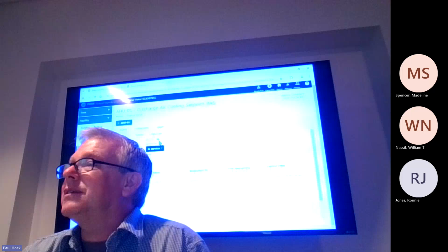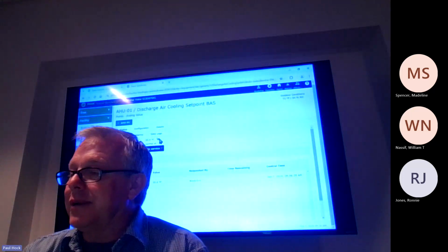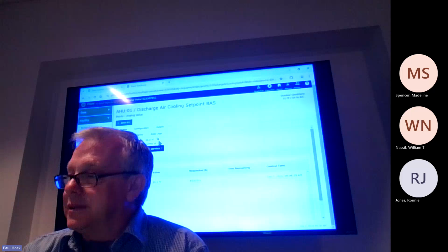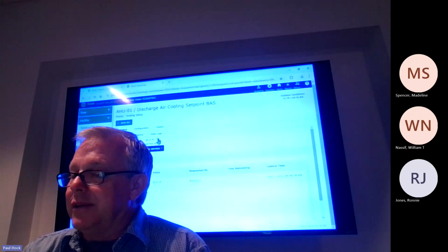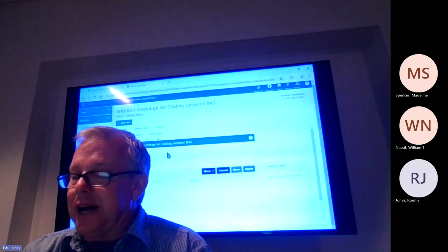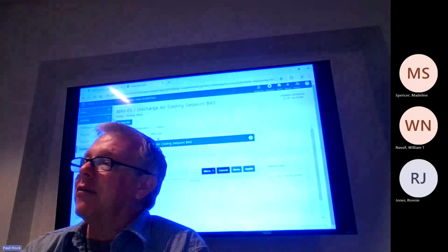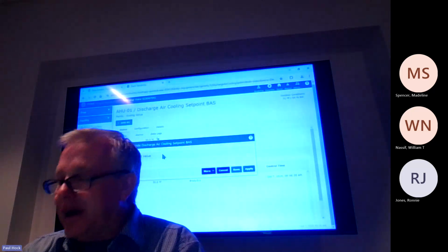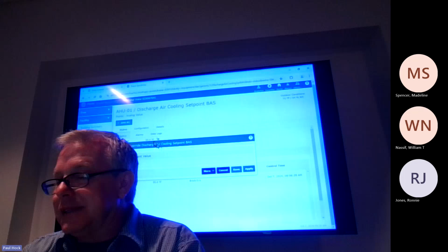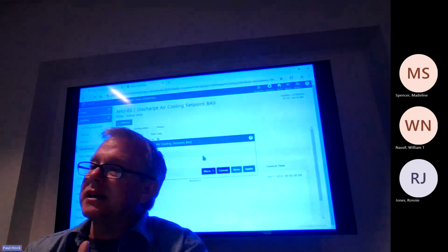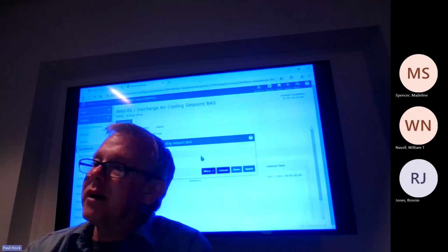So if you see that green box right there, it means it's overridden. Anytime you see the blue arrow with the green box, that means it's been overridden. Now, if I time it, you'll see a little clock in that green box. It means it's a timed override, like if you set it for 2 hours. But since there's no time clock on it, it's the permanent override. So whenever you do it from the spaces like that, it's going to give you a permanent override.